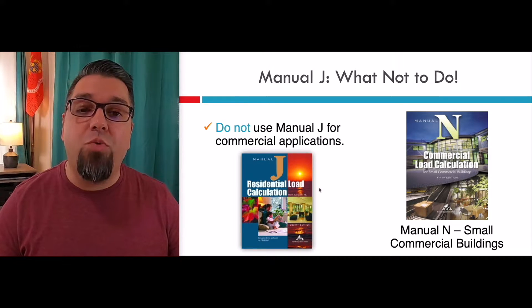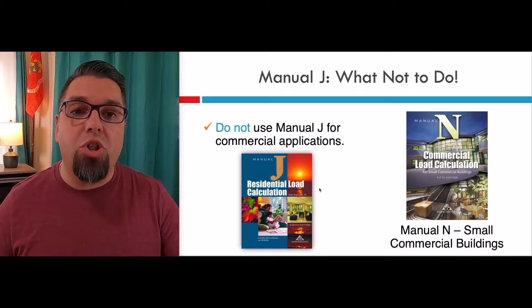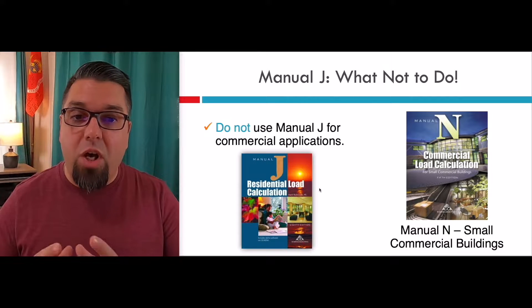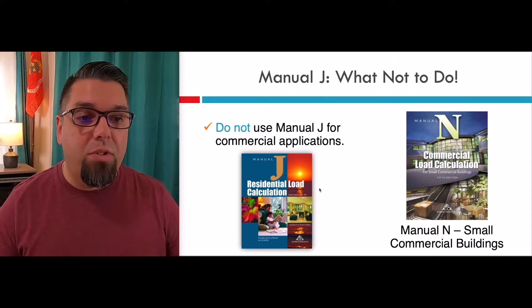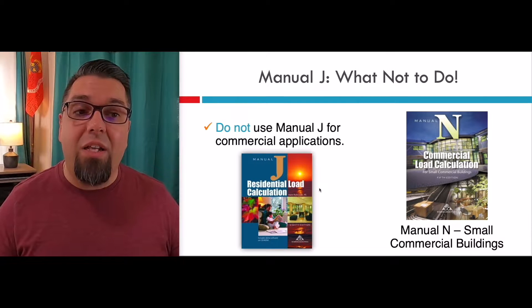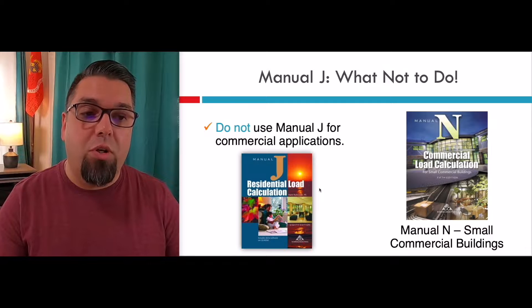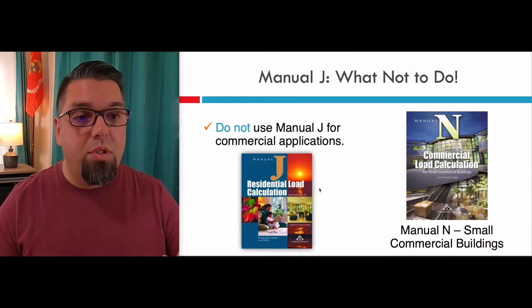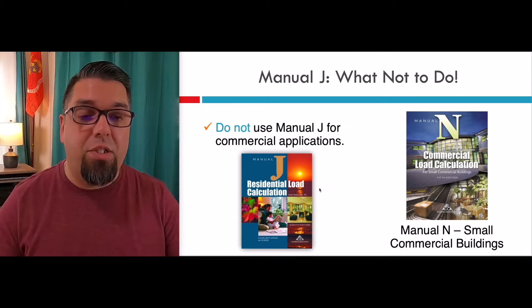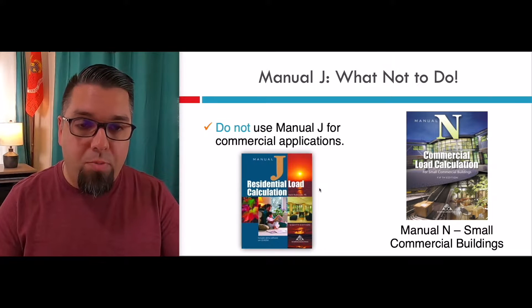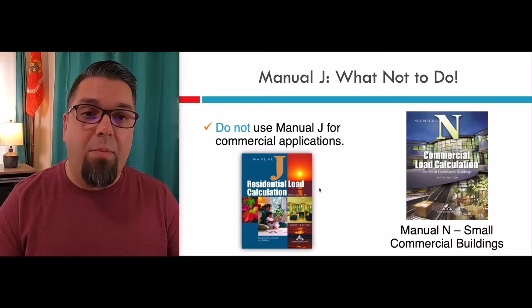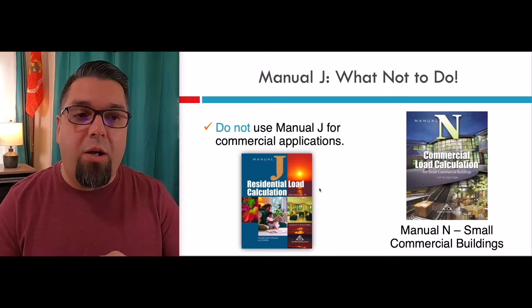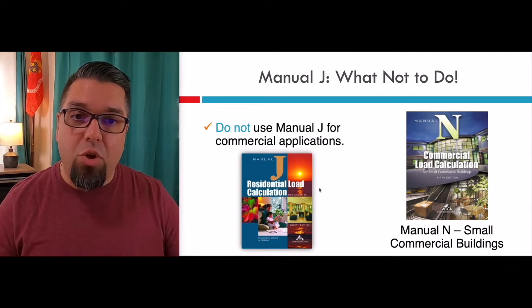First item, right off the bat: we do not use Manual J for commercial or light commercial applications. If you're going to do commercial applications, whether it's with software or longhand, you're going to use Manual N. Manual N is commercial load calculations — the equivalent for commercial loads. This covers everything from IT rooms to kitchens, restaurants, and schools. All of that runs through Manual N. Don't use Manual J — we're not going to account for things like lighting or occupancy the same way as Manual J.